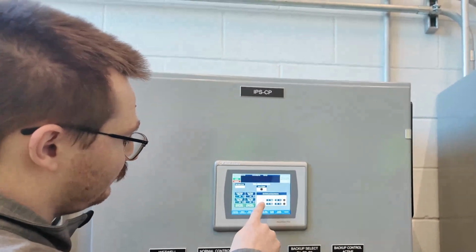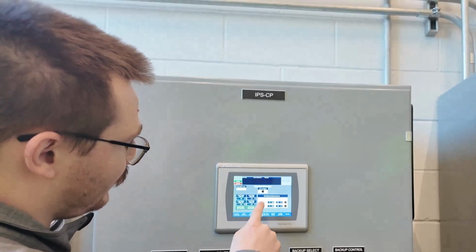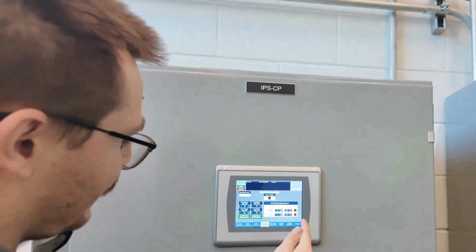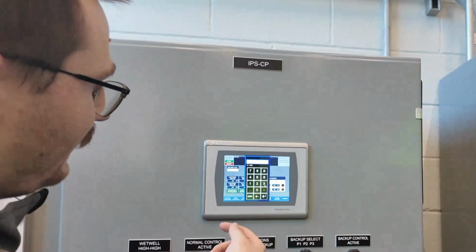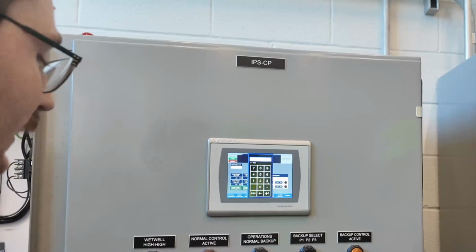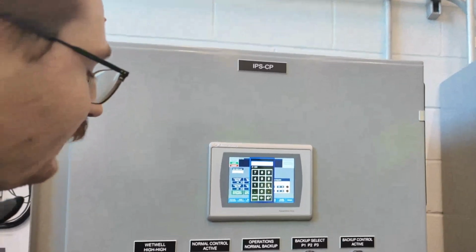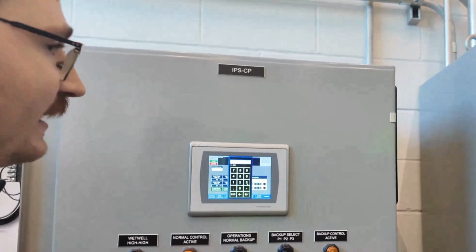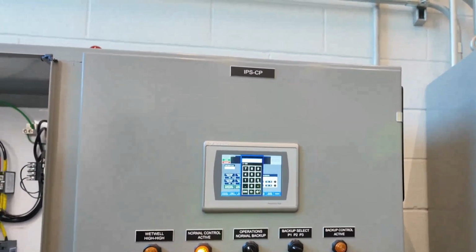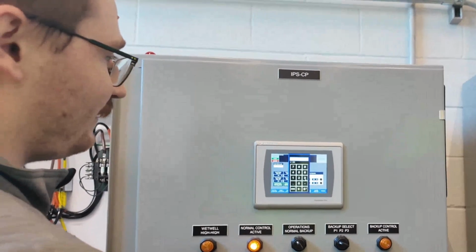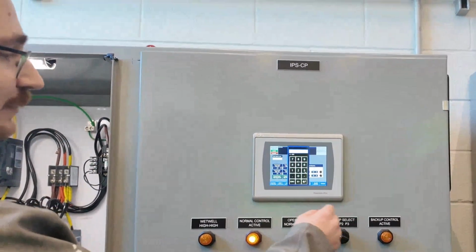We also have alarm set points. So you can enable and disable these alarms with the check marks. Check mark is good, it's enabled; X, disabled. And then you have alarm delays. So if the input comes in, you can change how long you want to wait until you actually get the alarm. I know sometimes some floats will get hit around in wells, so you can extend that. After like 10 seconds, if it's up for 10 seconds, you're definitely at a high level. That's when it'll alarm out.